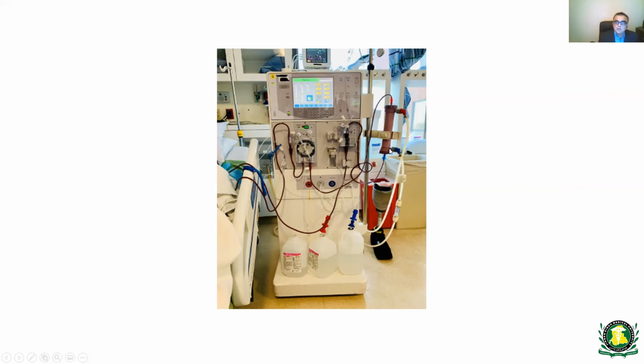The dialysate fluid goes from bottom to top in a countercurrent mechanism, just like we have a countercurrent mechanism in the kidneys, the loop of Henle between medulla and cortex. And then exchanges occur here; diffusion, convective forces and hydrostatic forces remove the fluid and toxic waste products. Then relatively cleaner blood goes back through this tubing. There's an air bubble filled chamber, and then it goes back to the patient's body.